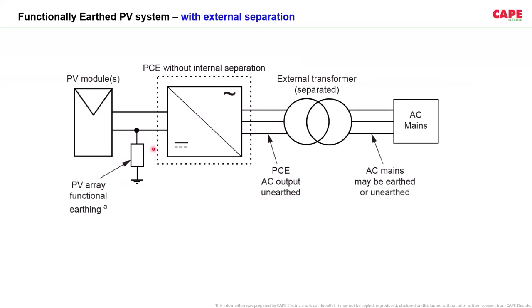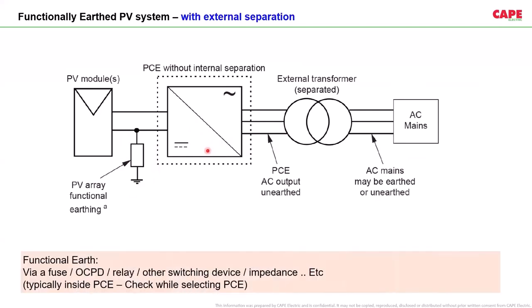Functionally earthed means this earthing has a certain purpose. Number one, this earthing will create a stable voltage on that particular line from the secondary side of the transformer up to the last PV module. The voltage is stable, and very important, the functional earthing is always made with a kind of device. For example, at this circuit, PV array functional earthing, there can be a fuse, a protective device, a relay, some kind of switching device, or an impedance.